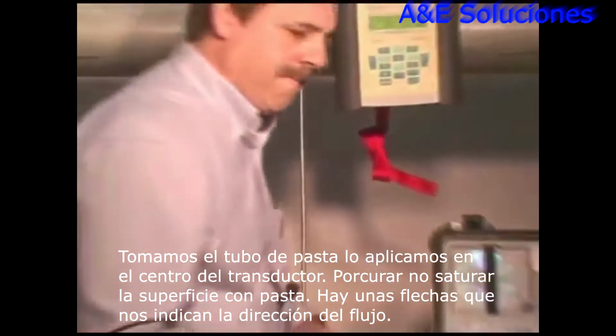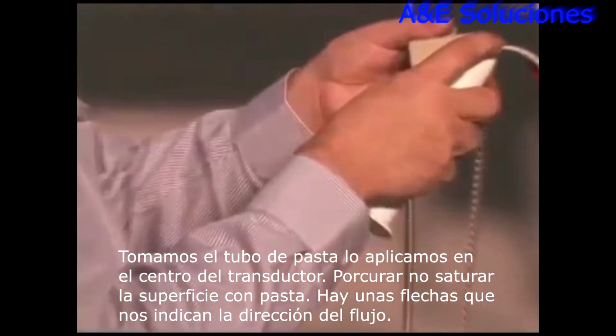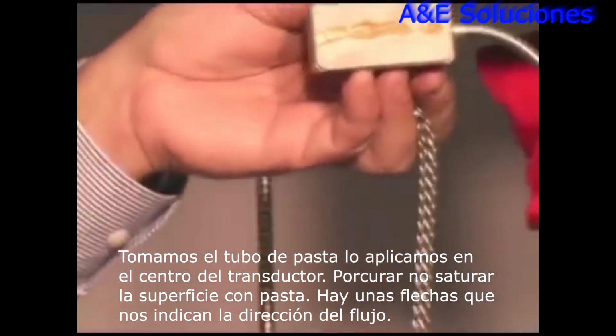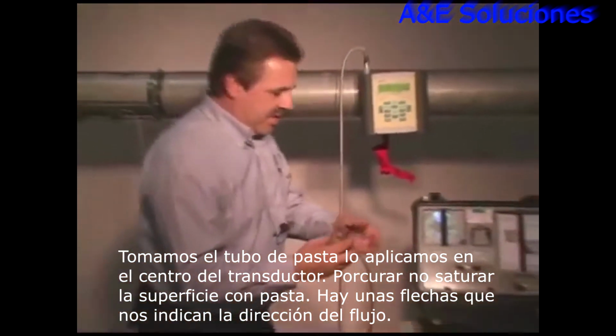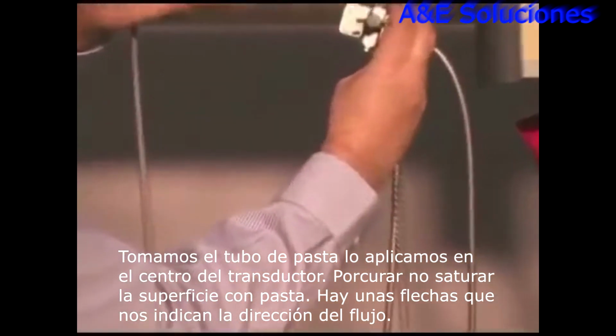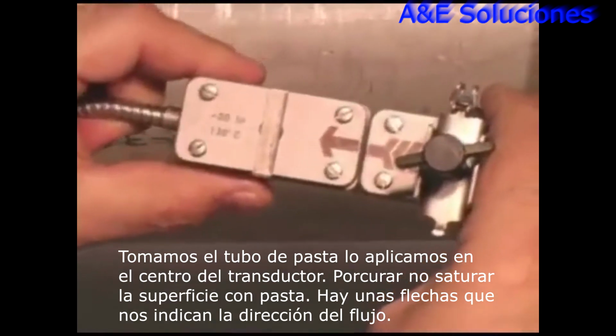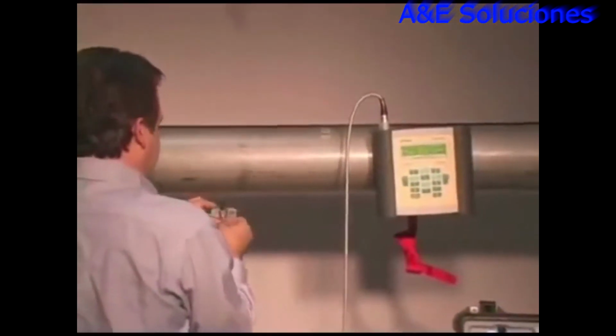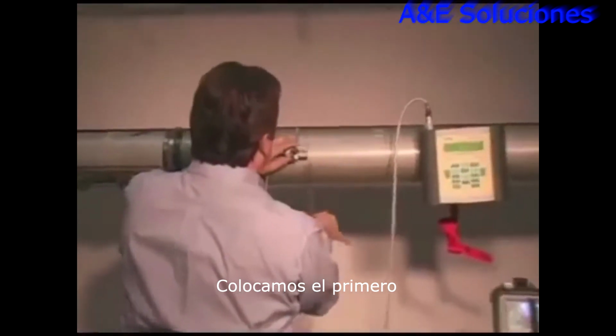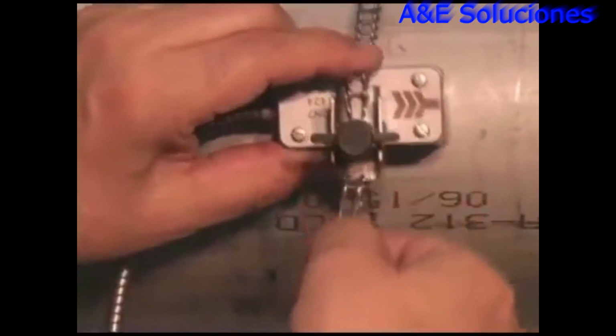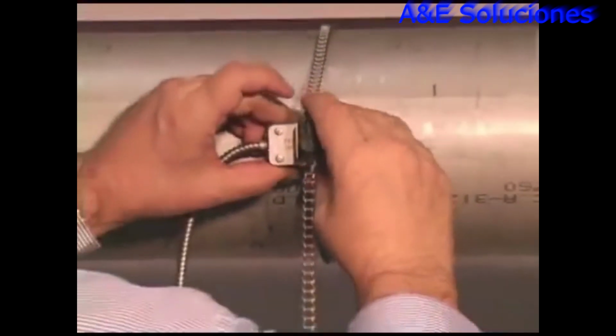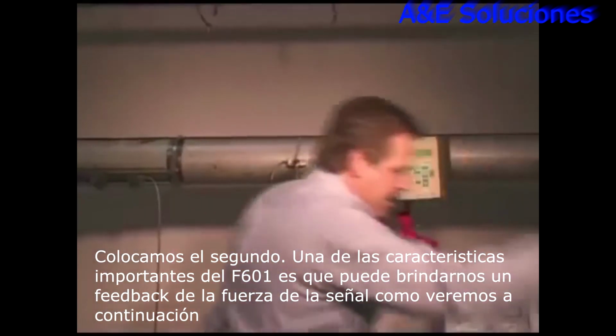Take out our coupling grease. Put a little bit of grease right down the center of the transducer. Don't have to overdo it. Now there's an arrow. If we hold these two transducers up, we'll see that we can make an arrow with that. Now that kind of makes it foolproof. What we want to do is face the arrow in the direction of flow. Now on this pipe, the flow is going this way. So we're going to face it that way. Okay, so we'll get the first one up there. Second one.